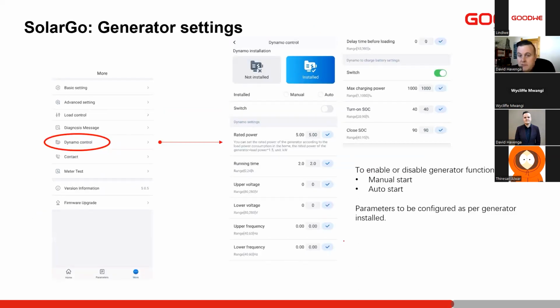Then looking at dynamo control or generator, we'll probably change it sometime to generator. But yeah, we can control that generator relay that I mentioned earlier, as well as the power. One thing that's important to keep in mind is that the smart meter must be off when the grid is off. Even when you're running a generator, the smart meter needs to be off, because it's one of the flags for the inverter to tell that the grid is off.